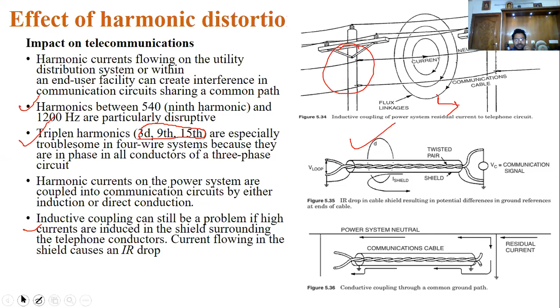Okay, so these triplen harmonics, as I said, are very dangerous to the power system. They will damage the system. Because you are running transmission lines and telecommunication cables at the same time, it will lead to some problems. It will produce noises in the telecommunication equipment. You know that at a time you are listening to two or three voices, or some beep sounds, because of these problems.